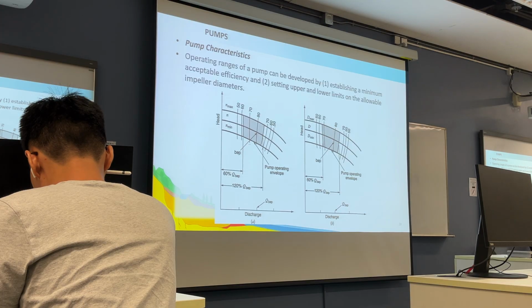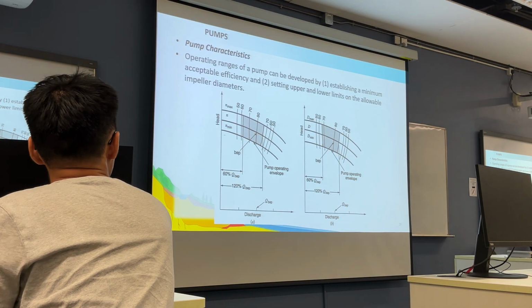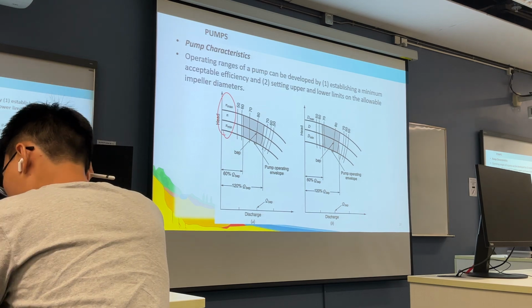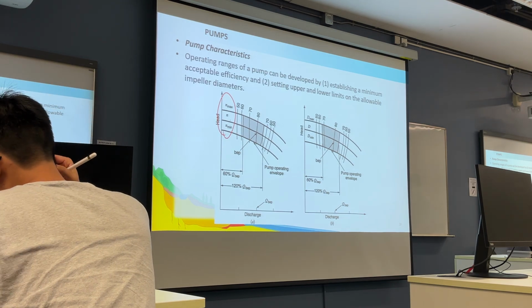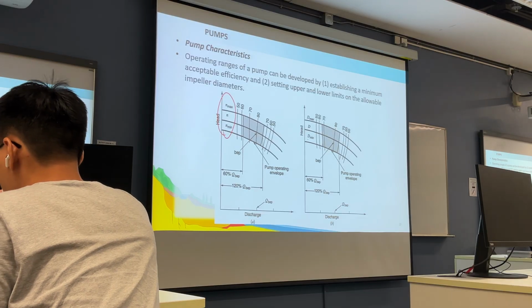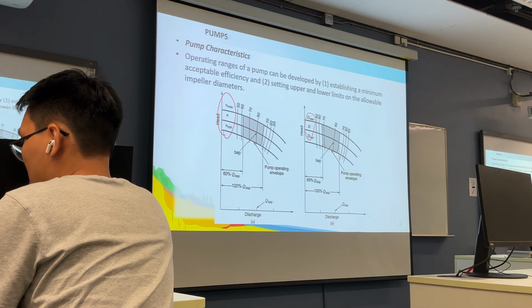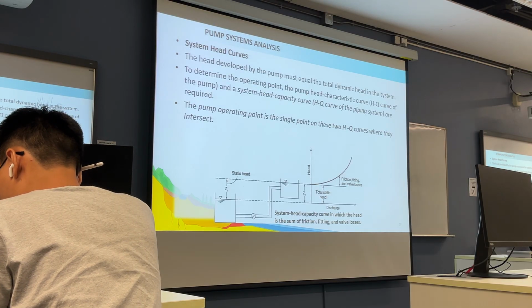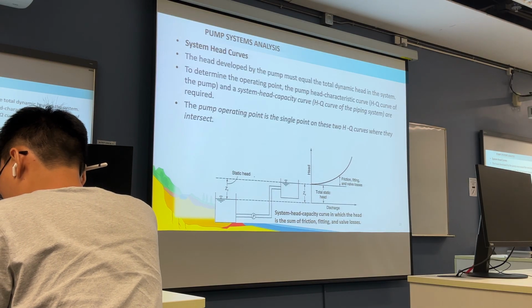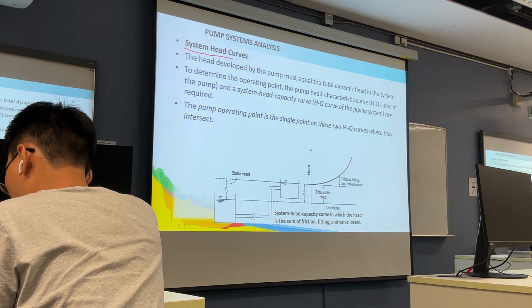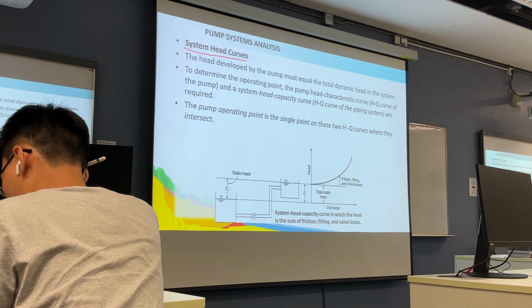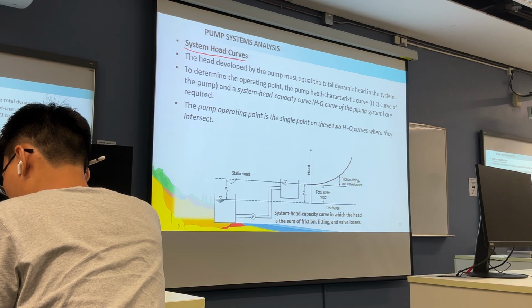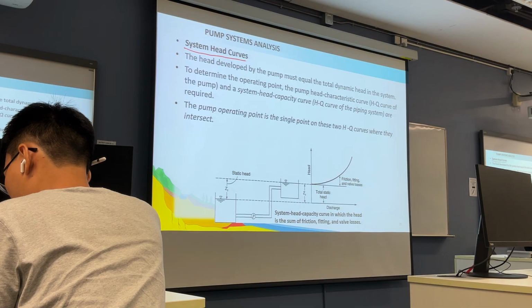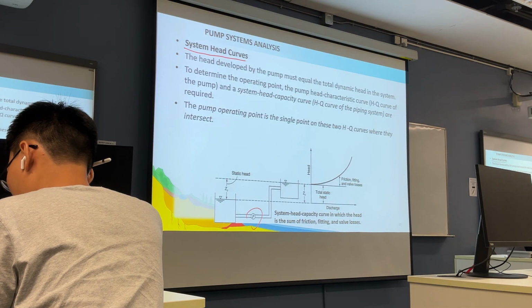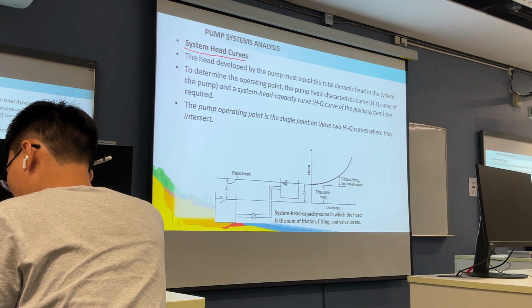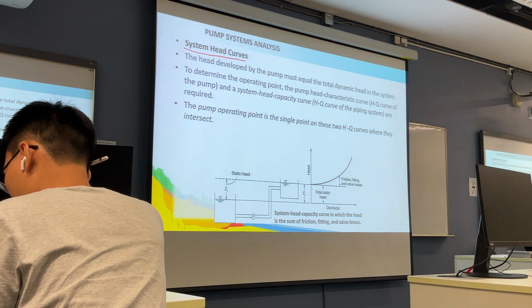This curve also talks about the range of the pump running for different rotational speeds, and for the same motor, different diameters of the blade, okay. Now, for the system head, we call it the system curve. Previously we talked about the pump characteristic curve, the pump itself, okay. The system curve talks about the system requirement for the pump in this system, okay.